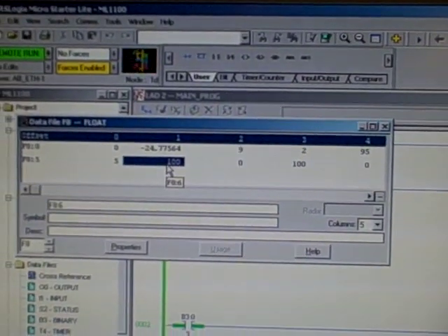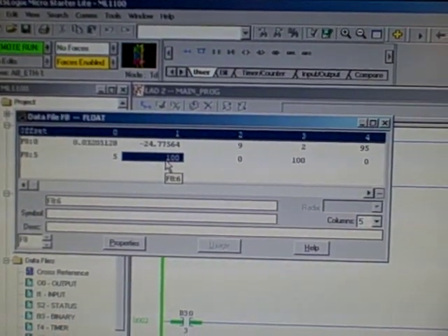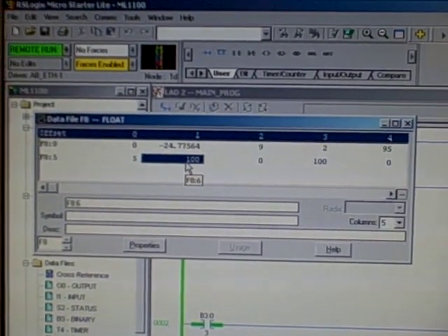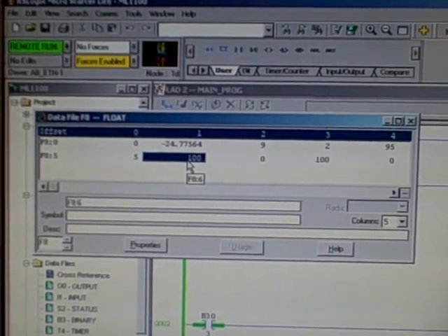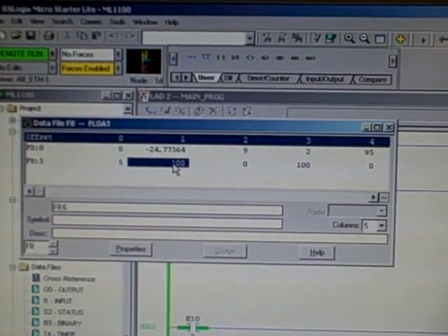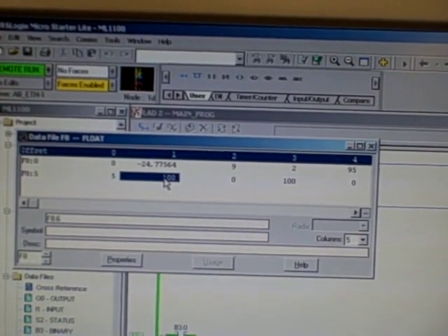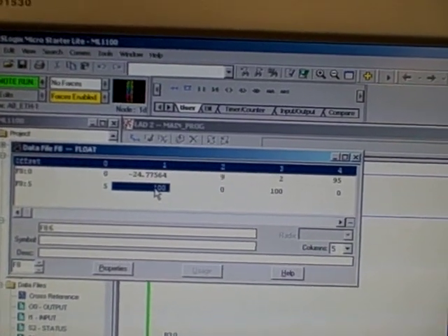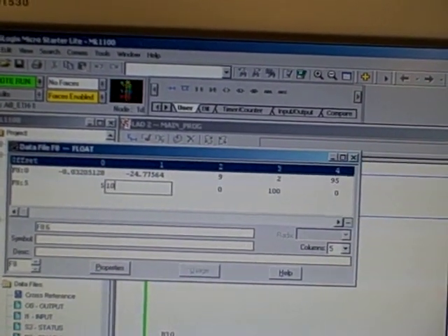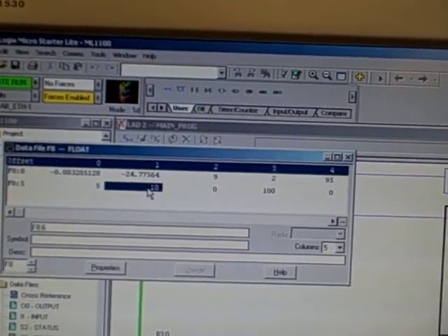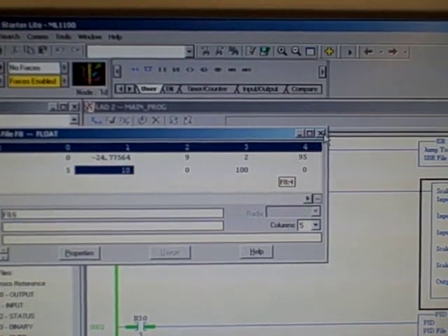So this is very convenient. We've made a change here that's an online parameter change. We did not have to save the program. We did not have to download to the PLC. We simply made an online parameter change, hit the enter key, and that is it. I'm going to put it back to 10, the way it was before.